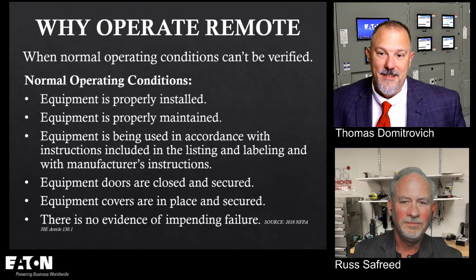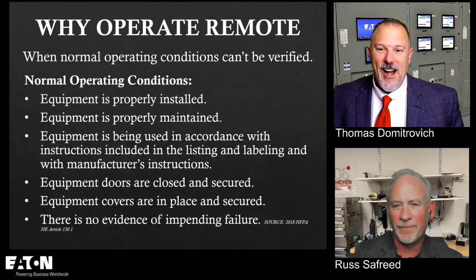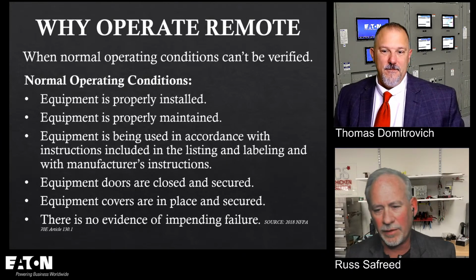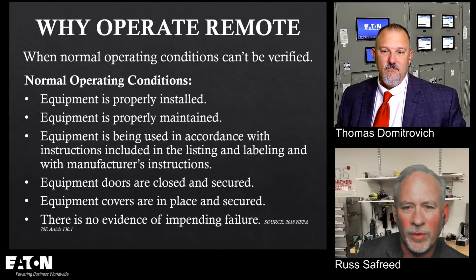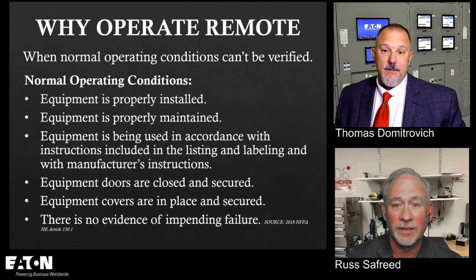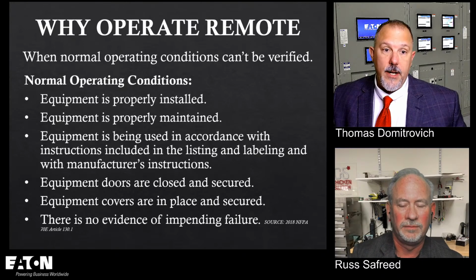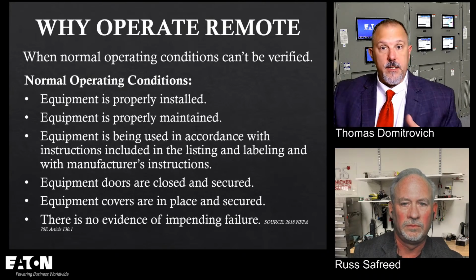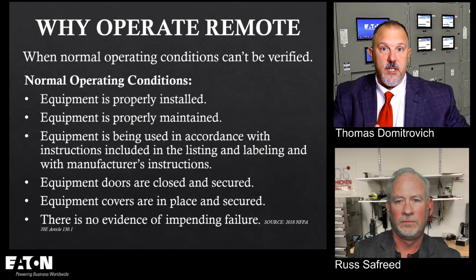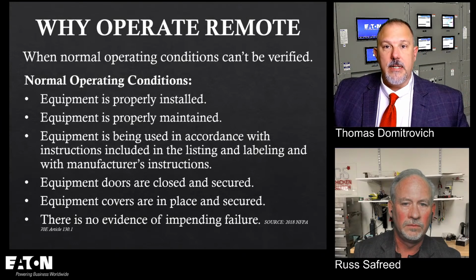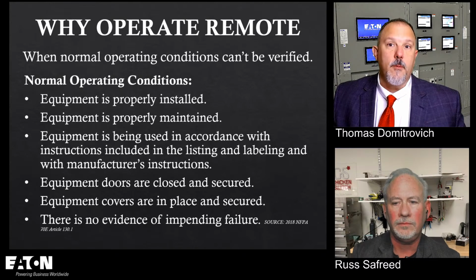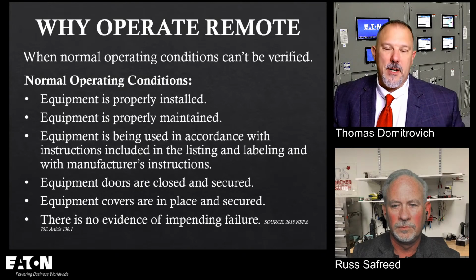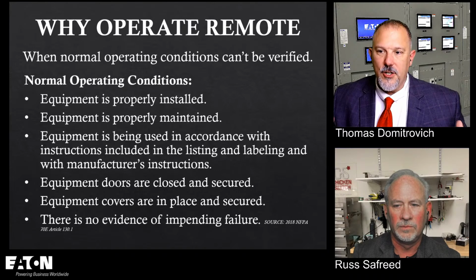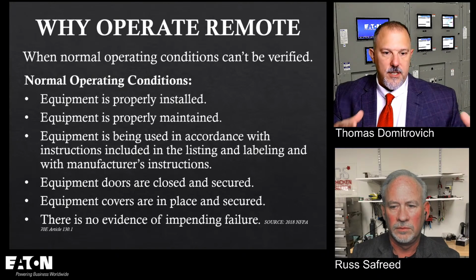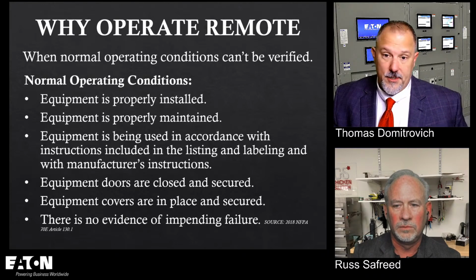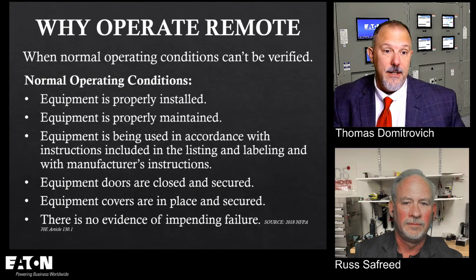You just installed something. It was just brand new built. And I think it's been years since I've seen it, but I think that first year of operation is one of your highest probabilities of having a problem. Yeah. You think about your plant, it's probably changing, right? You don't know if you caused an issue somewhere else, like you said, ancillary equipment. You may have this piece of equipment and you turn something on and off, and all of a sudden the equipment over here ends up in a compromised position because you're changing your power distribution system. You've got to make sure that you understand the condition of not just this equipment but other ancillary devices. To your point, those capacitors went, right. It might not be directly related to what you're looking at.